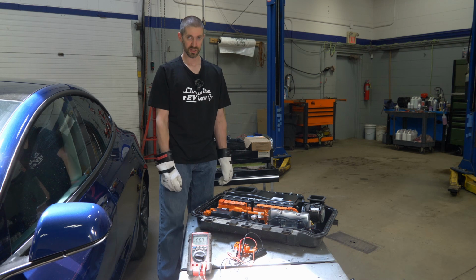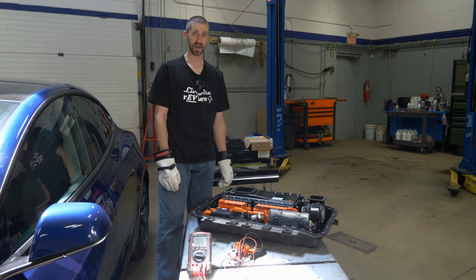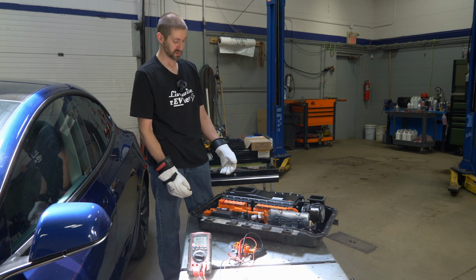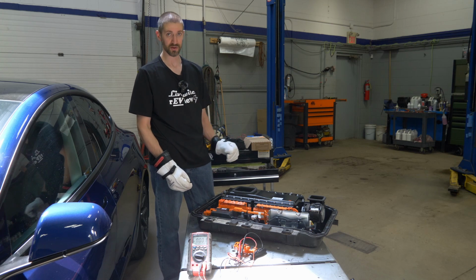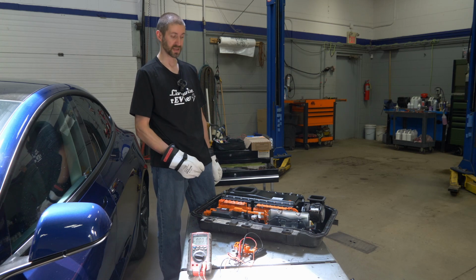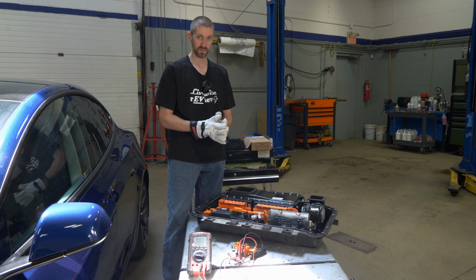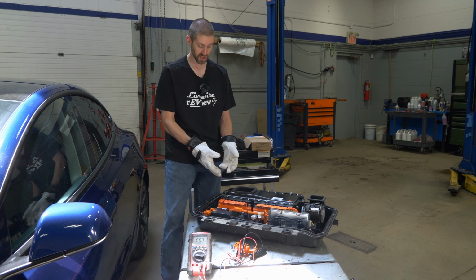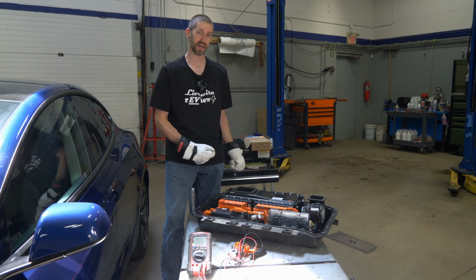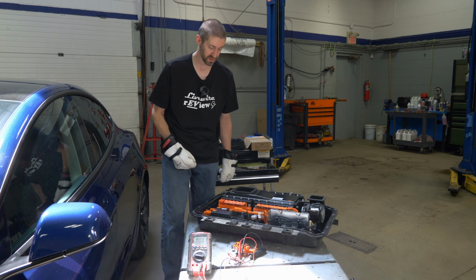So you would be able to change out that module since it is a fairly new battery, but if it wasn't a fairly new battery, what you would do is you would just match it up with a battery of a similar age, make sure it has the same voltage. So when you go to rebuild these batteries, you actually have to make sure that each module is at exactly the same voltage before you attach the bus bars.